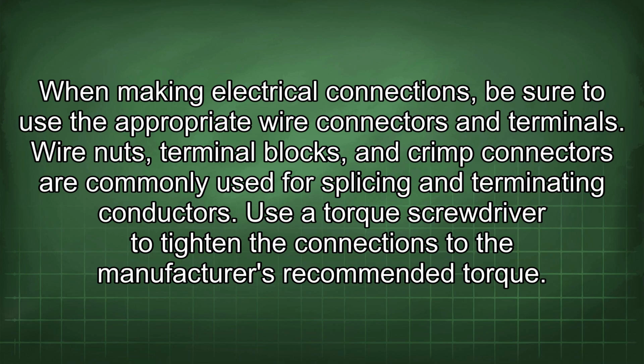When making electrical connections, be sure to use the appropriate wire connectors and terminals. Wire nuts, terminal blocks, and crimp connectors are commonly used for splicing and terminating conductors. Use a torque screwdriver to tighten the connections to the manufacturer's recommended torque.